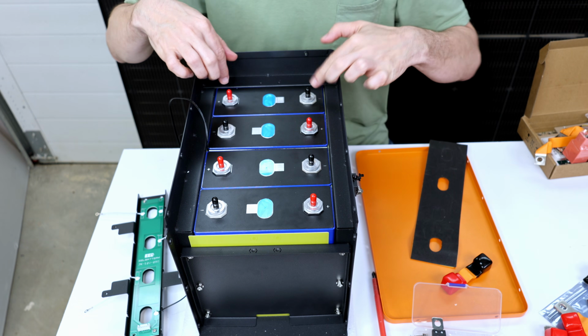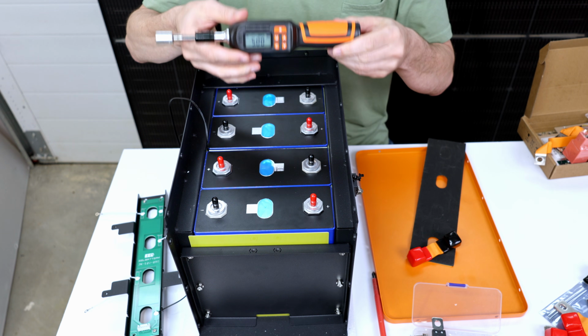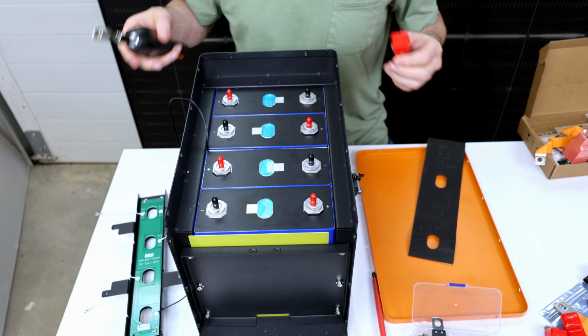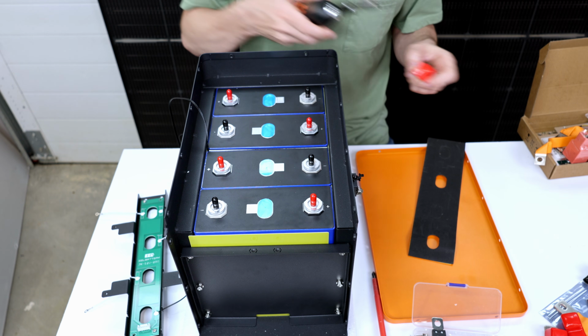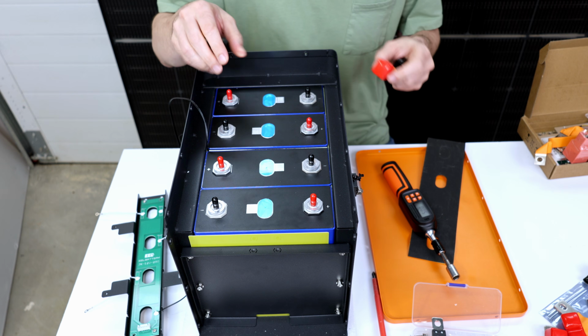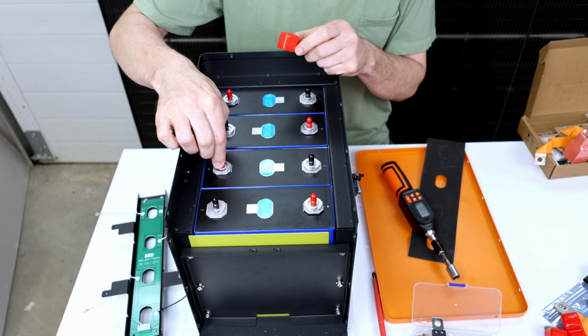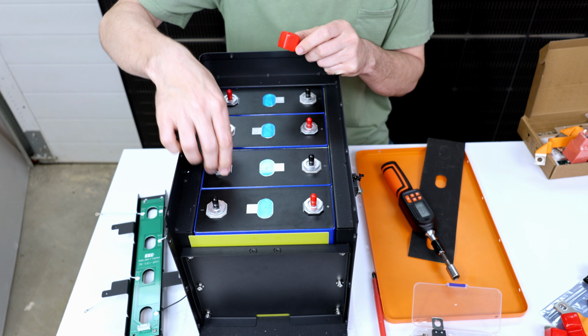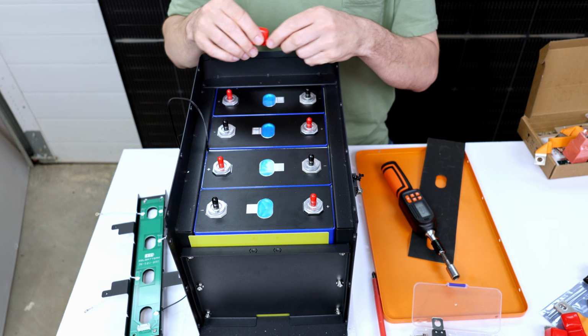Now, with our batteries in position, set the torque wrench to 5 Newton meters. And you do want to use a torque wrench for these. They need to be set to the right amount. If you don't get them tight enough, you're going to have heat issues. And if you get them too tight, you can strip the studs, and neither one of those is a good scenario.